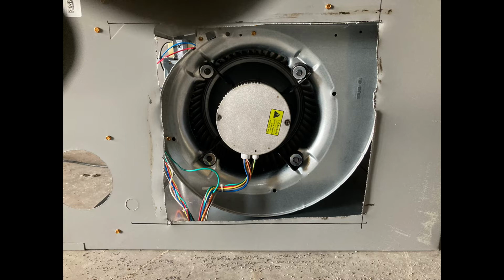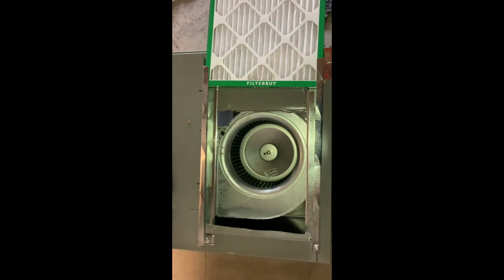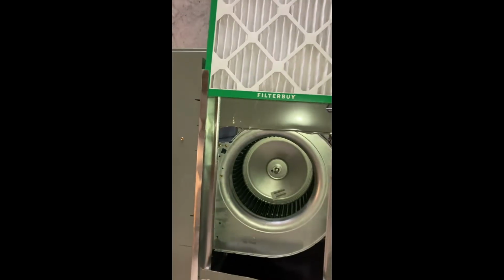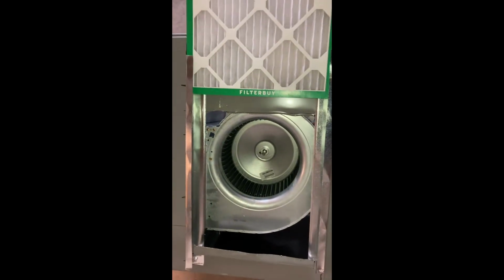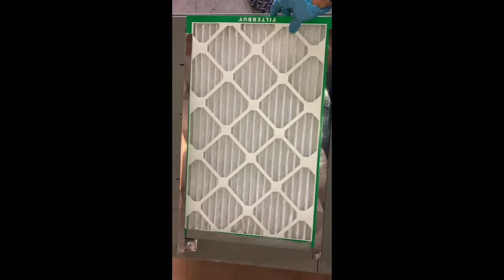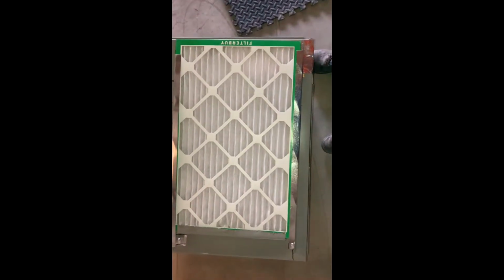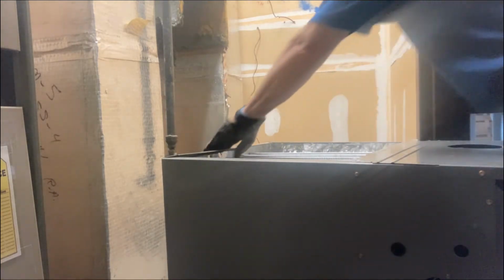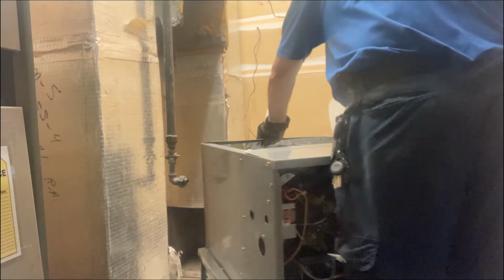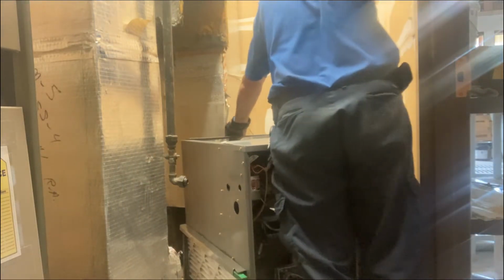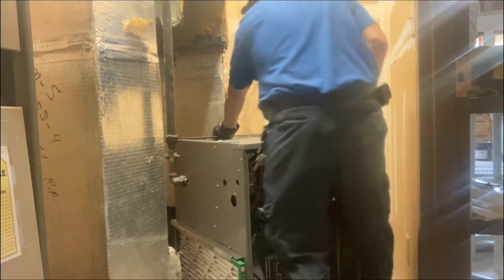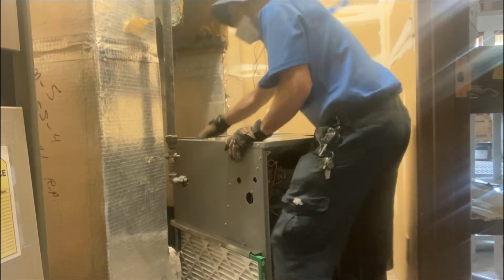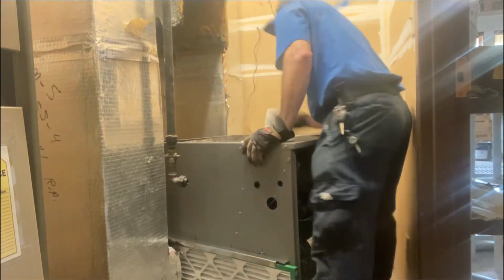The next step would be to install return filters on this unit. So you can buy ready-made filter racks or filter rails, or you can bend your own with some tin snips, measuring tape, and a hand metal bender. That's what I did here. I'll go ahead and slide the new air handler in place. We'll place a new A coil on top. And hook up our gas line, high voltage, low voltage power, and our plenum.